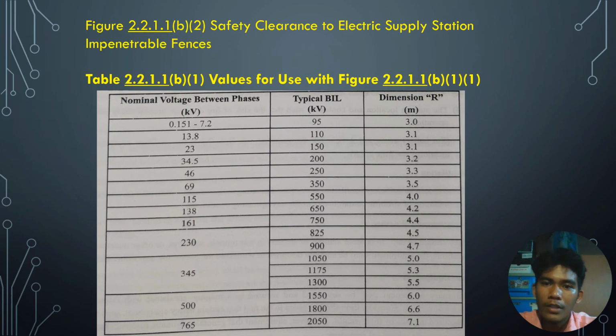Safety clearance to electric supply station impenetrable fences. So these are the limit distances from live parts to the fences. Example: for nominal voltage between phases of 0.151 to 7.2 kilovolts, the limit of the distance from the live parts to the fences is 3 meters, and for the typical 95 kilovolts have a limit of 3 meters.